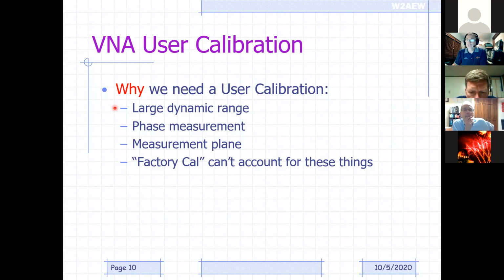So now obviously a calibration done at the factory can't account for these things, right? Because it doesn't know what you're hooking up. It doesn't know what the cables are. It doesn't know how you're using it. So you can't just have a factory cal do everything like an oscilloscope, for example, because here we're measuring things that are kind of beyond what the factory can account for. So that's the reason you do a user calibration.